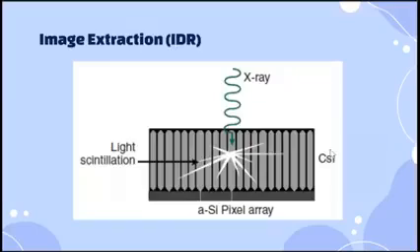Okay. Now, for the indirect radiography, this involves the amorphous silicon and cesium iodide or gadolinium oxysulfide scintillators. Okay, so let's go into detail. This phosphor screen scintillates or fluoresces when exposed to X-rays, emitting light that will strike the TFT detectors.